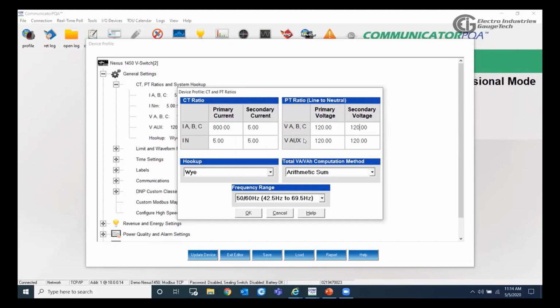And similar to that, we have also a fourth voltage input where we can have another source of voltage there. We can set the PT ratio for that at the V auxiliary. Then we have the system wiring, where we can choose between Y or delta or 2.5 elements, depending on the system there. And we have the volt amp and the volt amp hour computing method, which can be either the vector sum or the arithmetic sum. Then we have the frequency range. The default one would be 50, 60 hertz, and the other option would be the wideband auto.